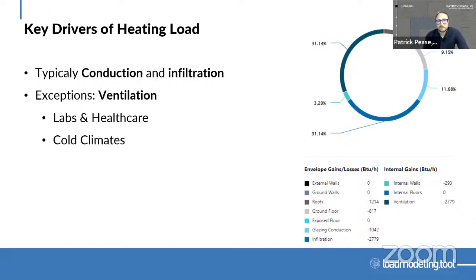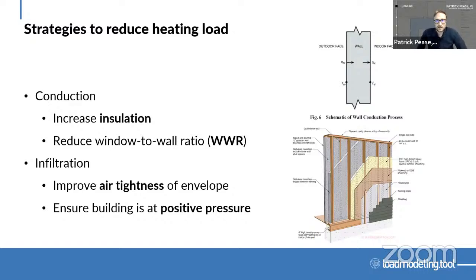Key drivers for heating load will typically be conduction or infiltration. The same exception applies for labs and healthcare — they have a lot more outdoor air which often drives the heating loads for those building types. In cold climates as well, even a small amount of outdoor air is really going to drive the load. For conduction, the primary mechanism is heat transfer through a wall surface, and ways to counteract that include increasing insulation to reduce heat transfer. We can also reduce the window-to-wall ratio — fewer windows — though that needs to be tied with daylight considerations. Windows are a significant source of load in projects.